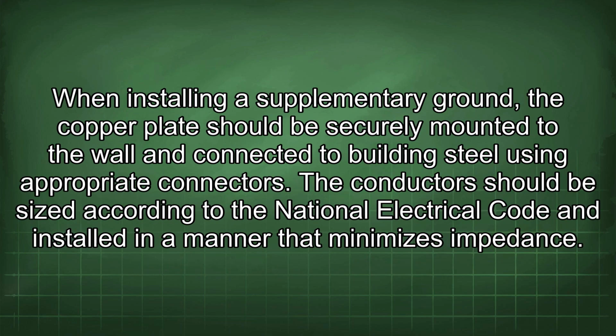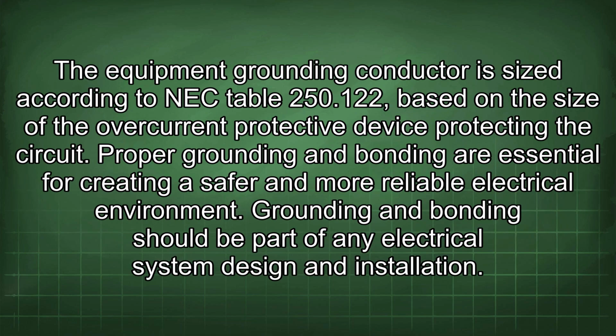When installing a supplementary ground, the copper plate should be securely mounted to the wall and connected to building steel using appropriate connectors. The conductors should be sized according to the National Electrical Code and installed in a manner that minimizes impedance. The equipment grounding conductor is sized according to NEC Table 250.122 based on the size of the overcurrent protective device protecting the circuit.